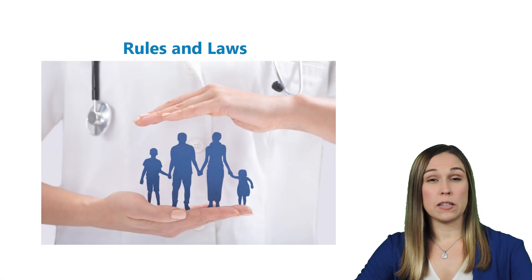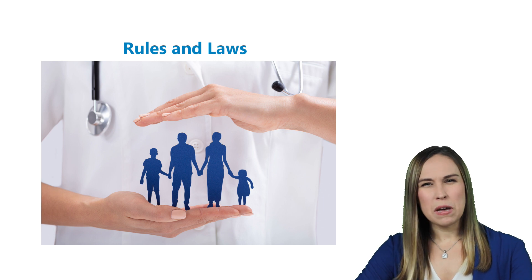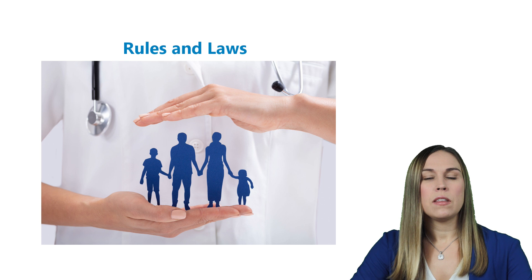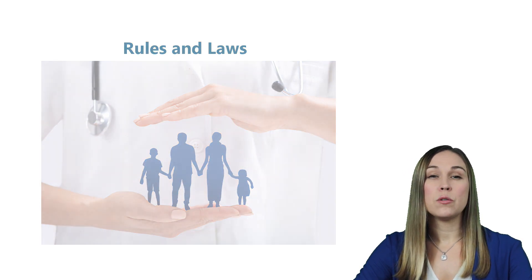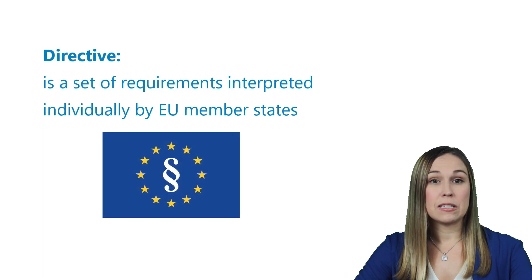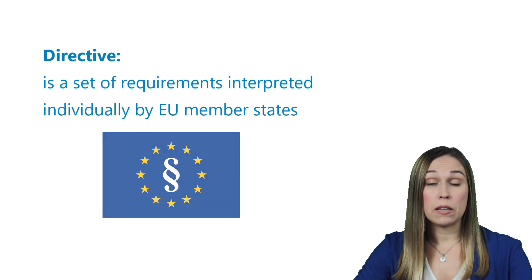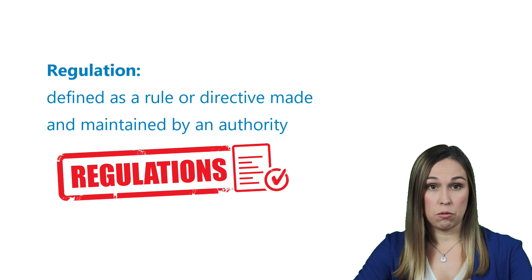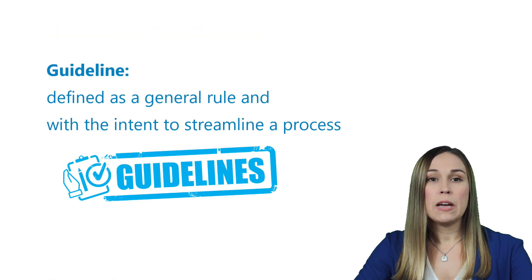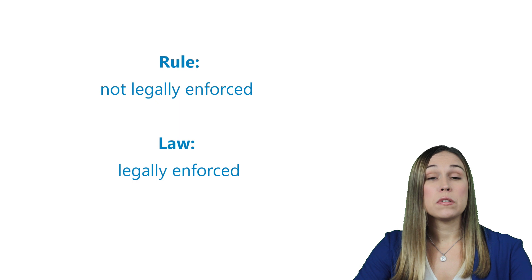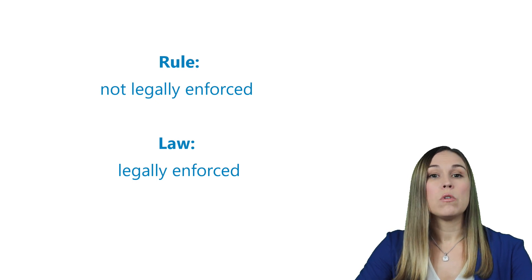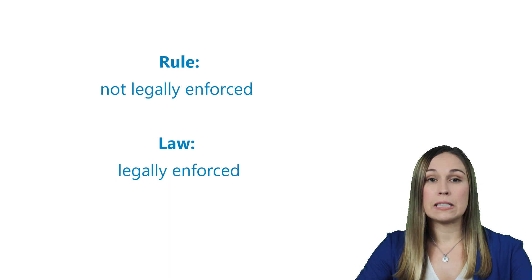When it comes to the rules and laws that govern medical device development, most people want to know: is this medical device safe? Where's the proof? These are fair questions, but before we answer them, it's important to understand a few key points. A directive is a set of requirements interpreted individually by EU member states — these are legally binding and supported by regulations and guidelines. A regulation is defined as a rule or directive made and maintained by an authority; these are not open to interpretation and are legally binding. A guideline is defined as a general rule with the intent to streamline a process, and is not legally binding. For the purposes of this video, we will consider a rule as not legally enforced and a law as legally enforced.